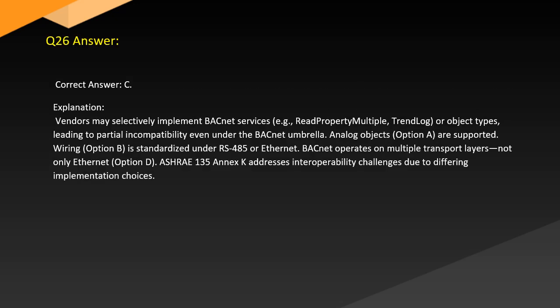Answer. Correct answer: C. Explanation. Vendors may selectively implement BACnet services, for example, ReadPropertyMultiple, trend log, or object types, leading to partial incompatibility even under the BACnet umbrella. Analog objects, option A, are supported. Wiring, option B, is standardized under RS-485 or Ethernet. BACnet operates on multiple transport layers, not only Ethernet, option D. ASHRAE 135 Annex K addresses interoperability challenges due to differing implementation choices.